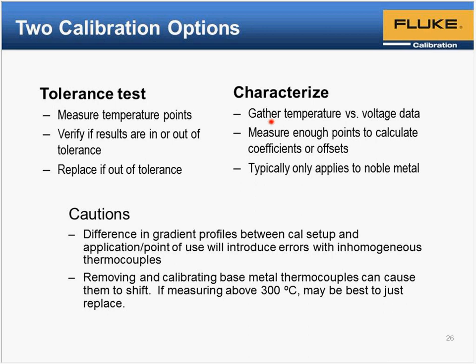Something really important to consider, especially with base metal thermocouples, but it also applies to noble metal, is that because the voltage is generated over a gradient region, if the calibration setup has a different gradient region than where the thermocouple is used, and the thermocouple wire is inhomogeneous, you get different results in the application versus when it's calibrated. So it gets controversial. Some have opinions that thermocouples can't be calibrated because of this.